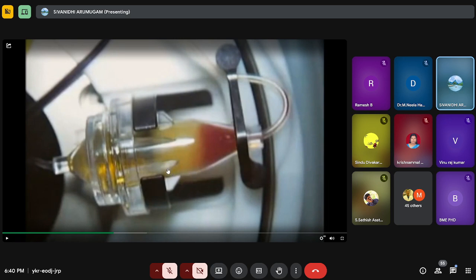So this is the important one, which separates the buffy coat, I mean the platelet and WBC, into the platelet. For example, this cone is called a leukoreduction cone. Leukoreduction means it removes WBC and gives only platelets. So this is a big topic, and I'm not going to explain it fully. Just you can see this cone will separate our buffy coat, platelet and plasma, into only platelets. The WBC will deposit in this cone only. It won't transfuse to the bag.